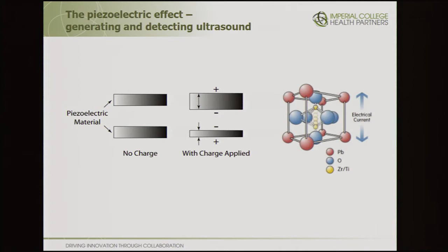And ultrasound is detected simply by the reverse of this effect. The ultrasound that's reflected by the object that's being imaged falls onto a piezoelectric crystal, making it vibrate. It's attached to a couple of electrodes, and you see an AC electric signal flow that's then analyzed to build up the ultrasound image.